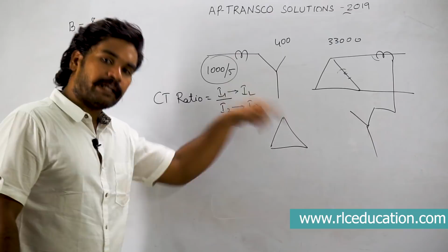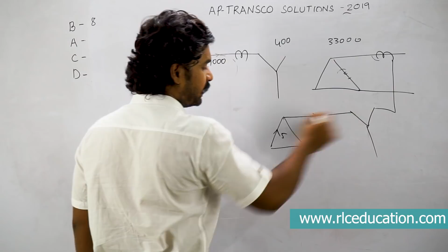Understood? So from this I can understand that 1000 by 5 is given on this side, meaning the line current here is 1000 amperes, then the phase current in the delta will be 5 amperes. Line current is 1000 and phase will be 5. If phase is 5, what will be the current in the circulating pilot wire? Pilot wire current will be 5 root 3. Now on the star side of the CT connection, what is the phase current? That is also 5 root 3, because in star, line and phase are the same.